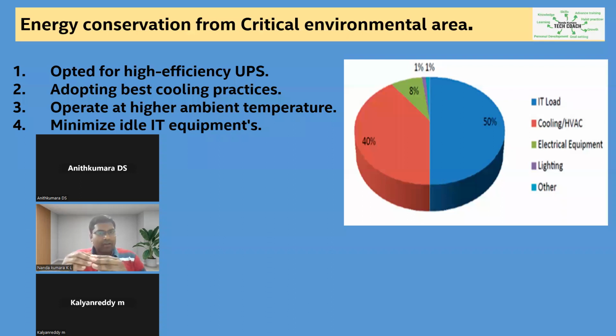Again, this depends on discussion with your team and the IT team as well, because sometimes it directly impacts the equipment. We have to think it over and work together with the data center team to set it. From 22 to 24 degrees you can set it directly. Anything up to 25 is good. Above 25, that is 26 and 27, needs proper discussion and conclusion.